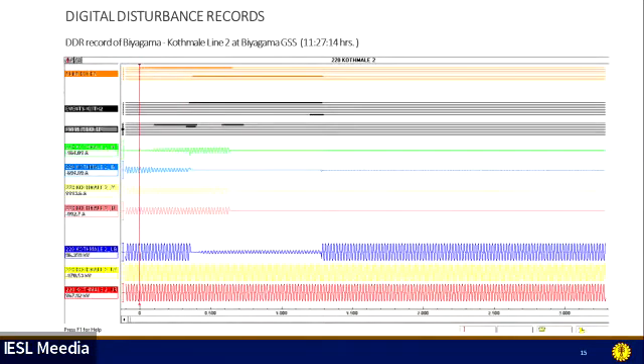So this is the digital disturbance record of the Biyagama Kothmale line 2, and in this portion it shows the slowly increasing neutral current. That is what we say is there was a small phase to ground earth fault, and at the same instant there is a small decrease in the blue phase current. So we interpreted that as a high impedance transient earth fault in this line. A similar record we found from the protection relay as well.